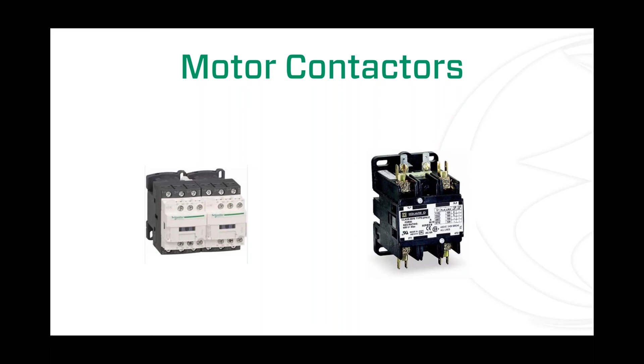Because these turn on and off heavy loads, they have heavy contacts inside, but every time that motor comes on or shuts off, there's a little arc of electricity that happens each time. Over time, those contacts are going to wear out, the material on it is going to wear off, or maybe the coil will simply fail inside the motor contactor. My point is that eventually, someday, these are going to burn up, they're going to fail, and they're going to need replaced. So again, this is a super simple little component, at the heart of just about every control panel out there—the motor contactor, something you'll see.